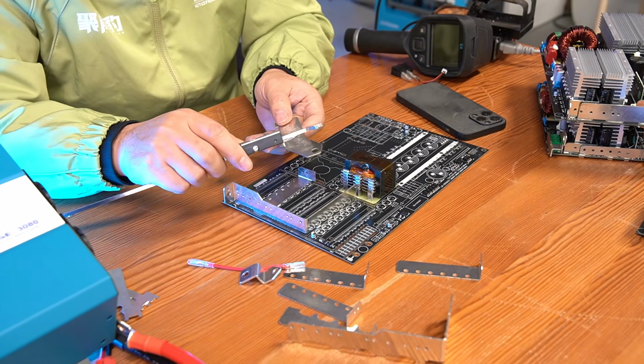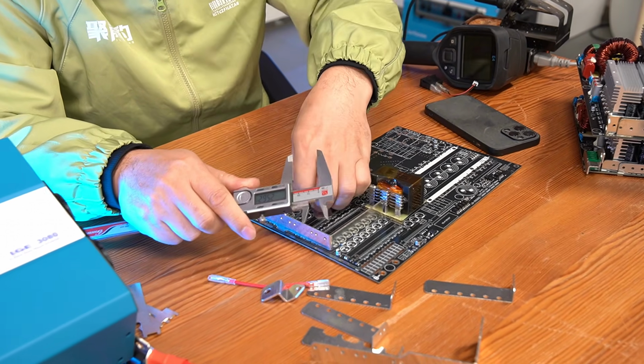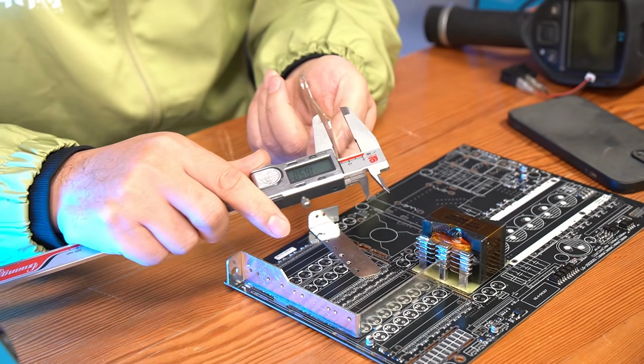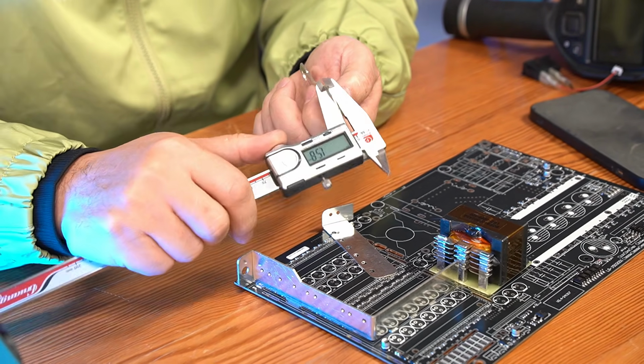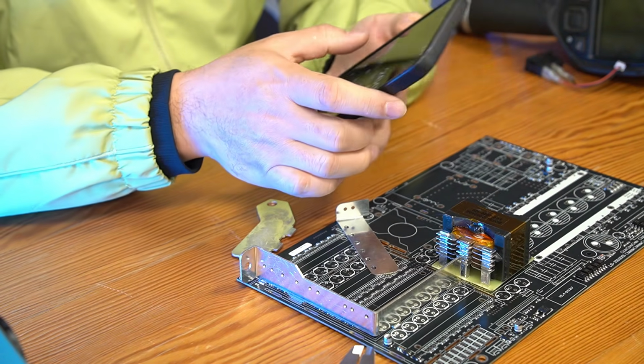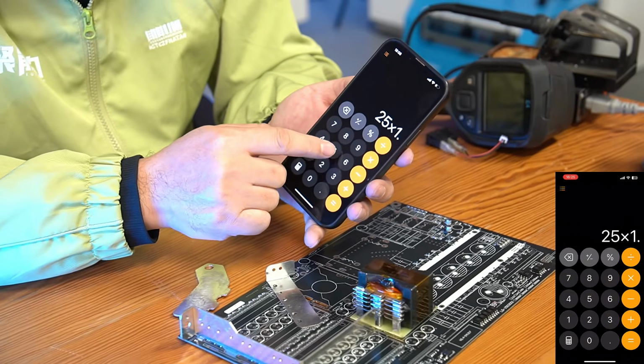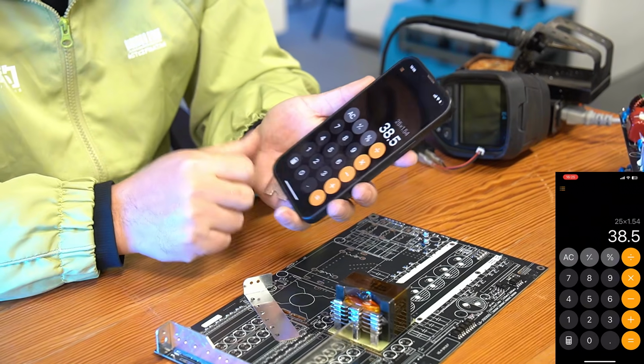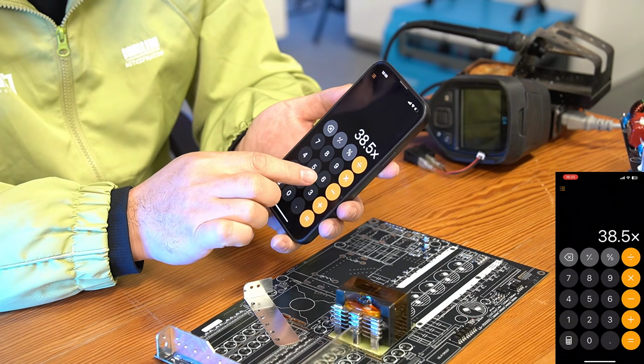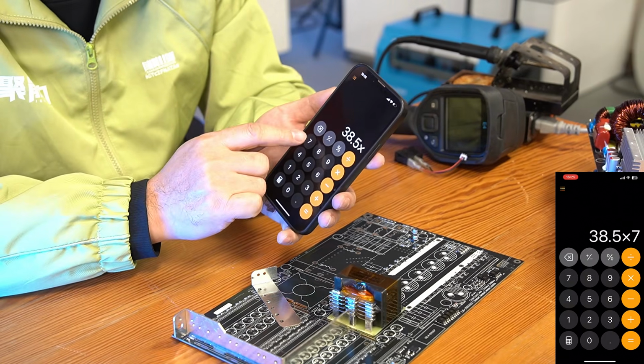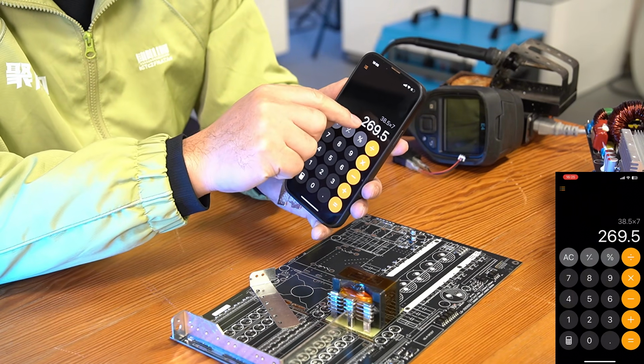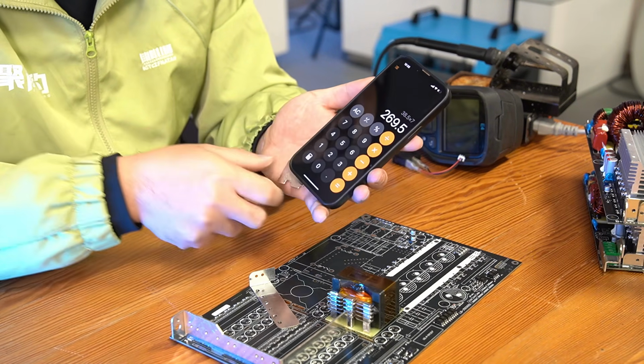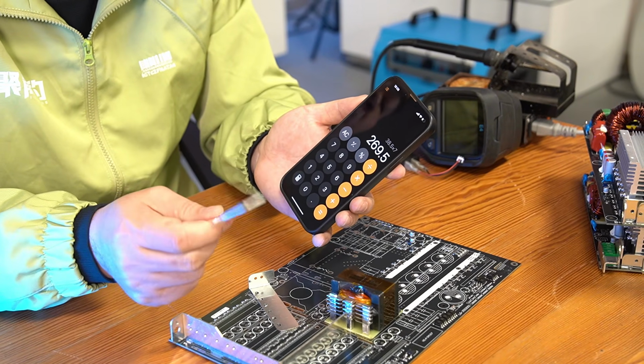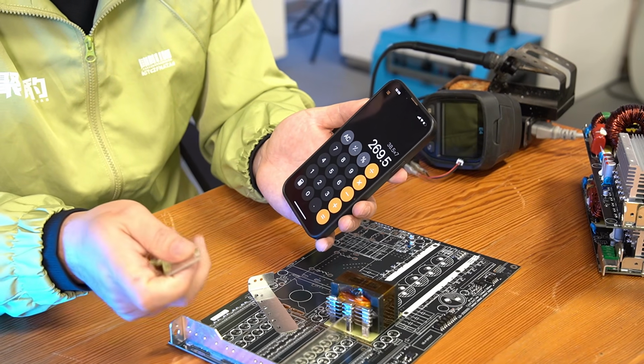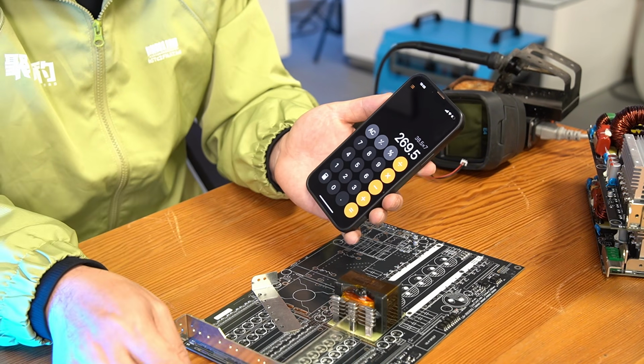This critical bus bar has a width of 25 mm, a thickness of 1.54 mm, and thus a cross-sectional area of 38.5 square millimeters. Over a short distance, it can carry 7 amperes per square millimeter, resulting in a total current capacity of 38.5 times 7 equals 269.5. Even at 269 amperes, the temperature of the bus bar remains below 60 degrees. Therefore, our design is not only excellent, but also highly rational.